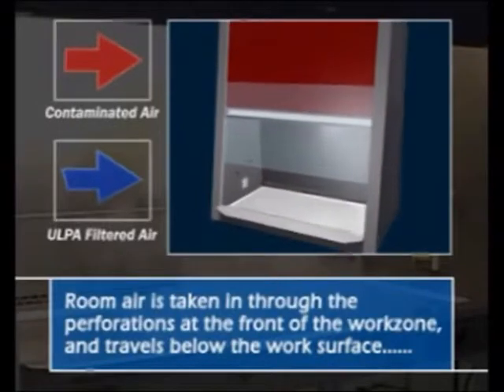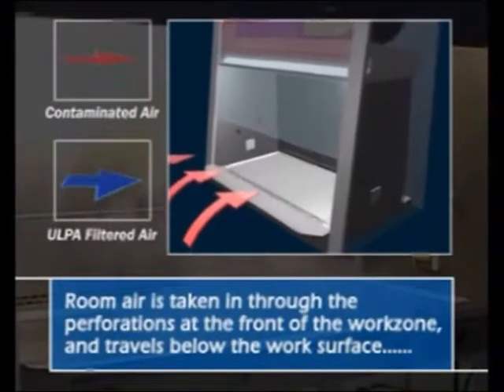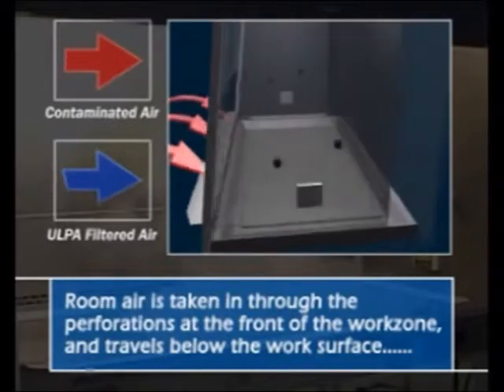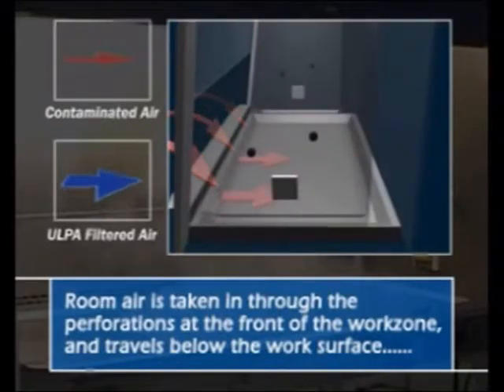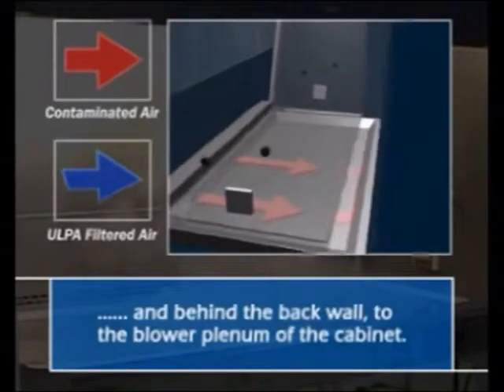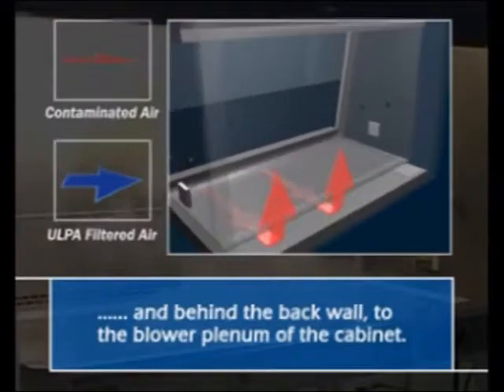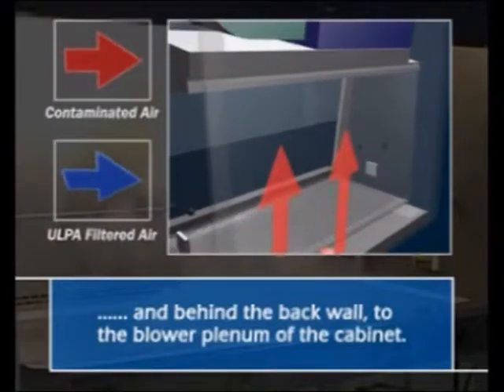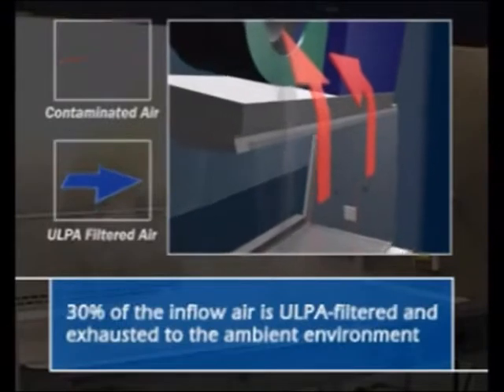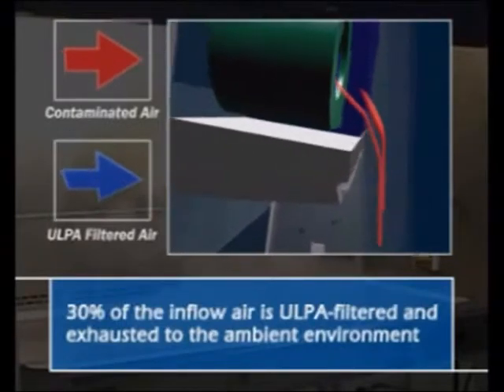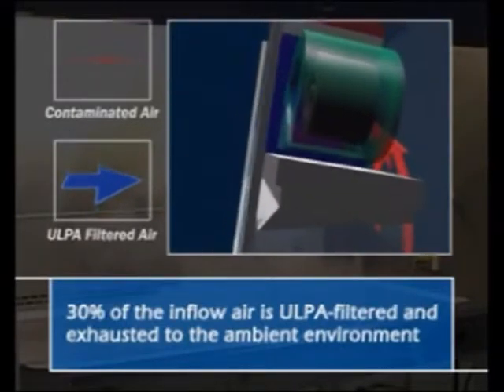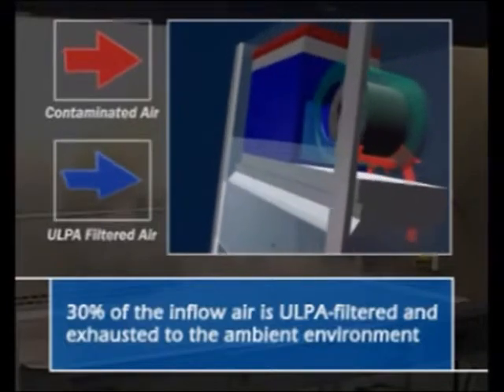A Class II Type A2 is a recirculating design biosafety cabinet. This means that room air is drawn into the cabinet through the front air grills, and travels below the work surface through the back of the cabinet and into the blower plenum. From the blower, the air passes through the ULPA filters. Approximately 30% of the air is ULPA filtered and exhausted to the surrounding environment.